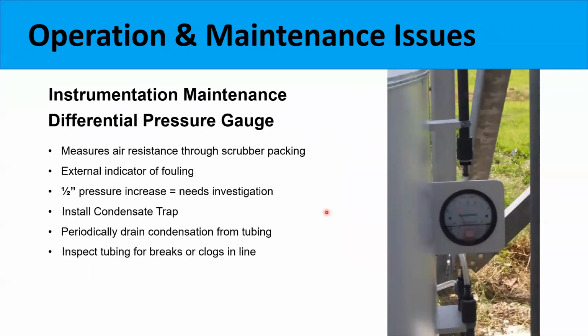Another piece of instrumentation that's very commonly found and important on a wet scrubber is that differential pressure gauge, whether it be a magnehelic gauge or an indicating gauge. You can have analog or digital. We often use Dwyer, or sometimes Rosemount as well.